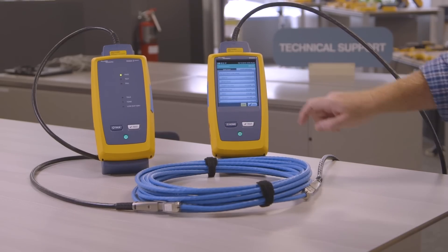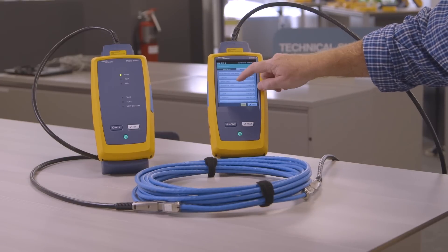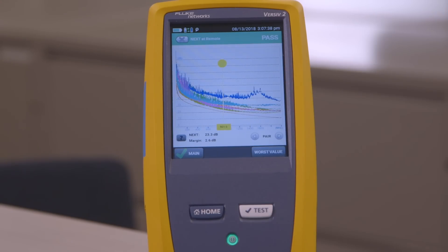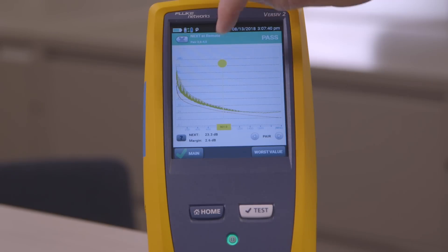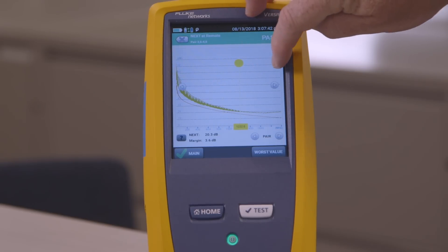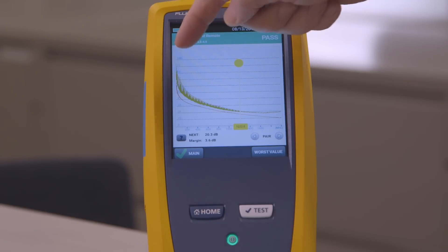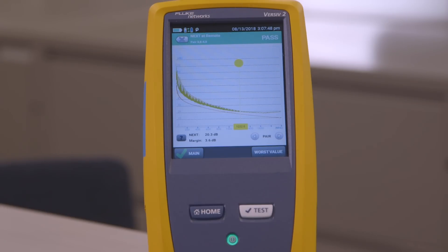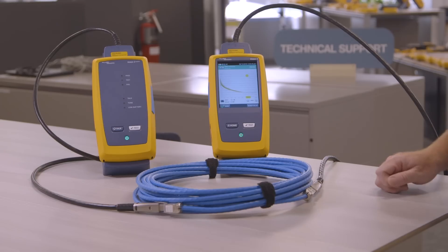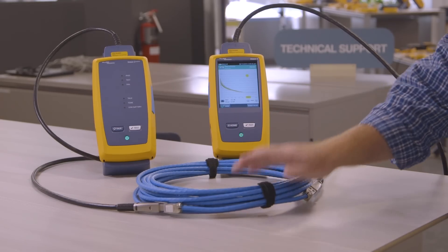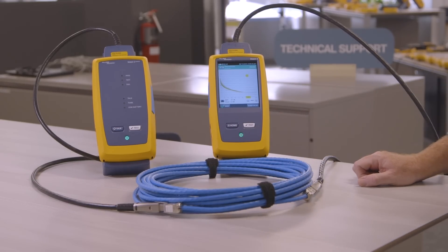We've passed the Category 8 test. And if I drill in on one of these noise parameters — let's take a look at NEXT — we can see that Category 5E goes to 100 megahertz, 6 to 250, 6A to 500, and Category 8 is going to go all the way out to 2 gigahertz. The red line on the bottom is the limit, and our measured values are passing. This cabling is ready to support the 25 and 40 gigabit standards of Ethernet.